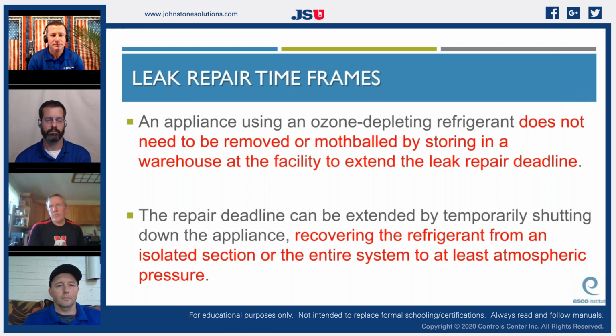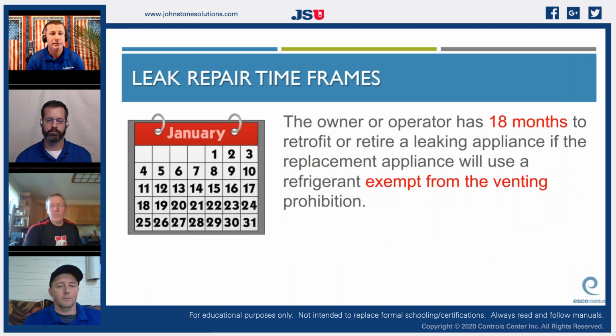And the one below it, there are system racks that I saw in a commercial building one time where they were able to isolate the leaking component by shutoff valves and recover that particular section without having to shut down the entire system. You betcha. Right. So that is mothballing it until you can make the repairs, I'm assuming.